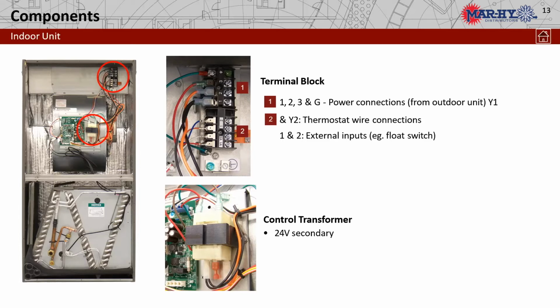Then as you look at the terminal block number 2, Y1 and Y2 are our thermostat connections. So it's only a 2-wire connection, and it's non-polarized sensitive. So it doesn't matter how you hook them up. So we shouldn't be able to mess this up, I hope. 1 and 2 are our external inputs. This is where we would connect our safety switches, be it float switches, pan drain switches, whatever. This is our forced off function, as we see with other manufacturers. There again, that will have to be addressed through our function settings to enable that to work correctly, but we will cover that shortly. You see a 24-volt transformer. That transformer does nothing more than run the strip heat sequencers. That's what that's there for.